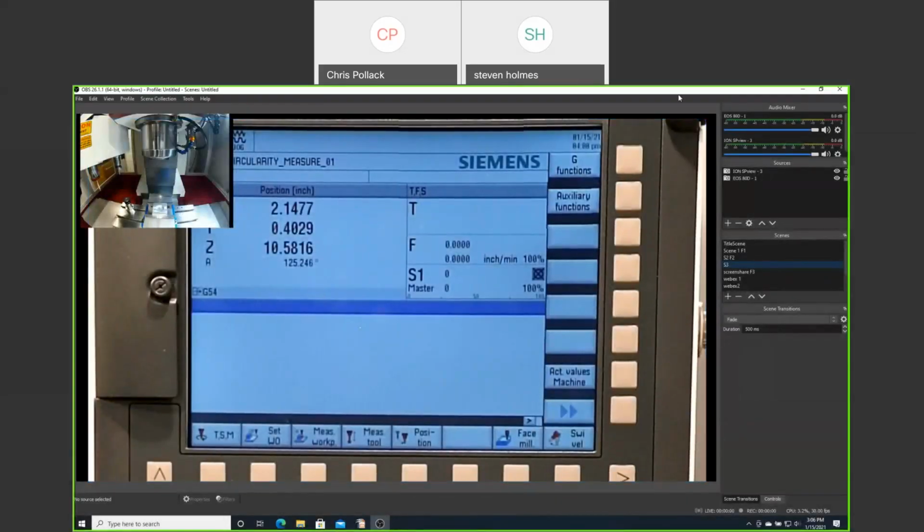Okay, so as Steve mentioned, a great way to validate if you're getting some form of inconsistent behavior on the machine. A good common area where you could see this is you're in process, the machine's running, and she just pauses. And maybe it's hung for a second, and then maybe it starts to move again. A lot of times, we're not sure what could be causing that. Well, believe it or not, it could be something as simple as a door prox switch not staying closed fully or on the hairy edge of that input. So how could I see that input is bouncing? How do I see that safety proxy to validate that the doors are closed or my air pressure is sufficient or a number of things?